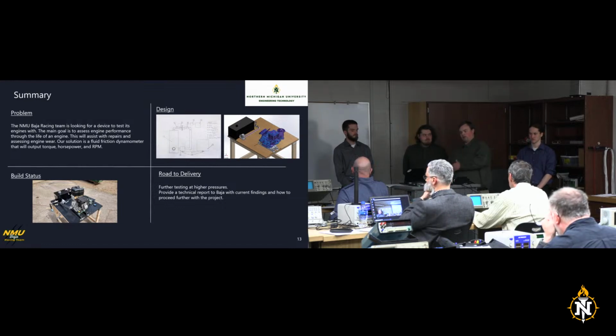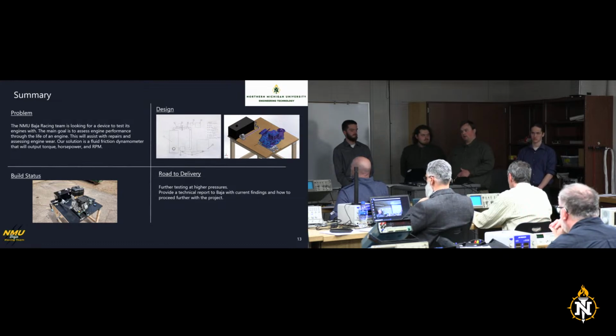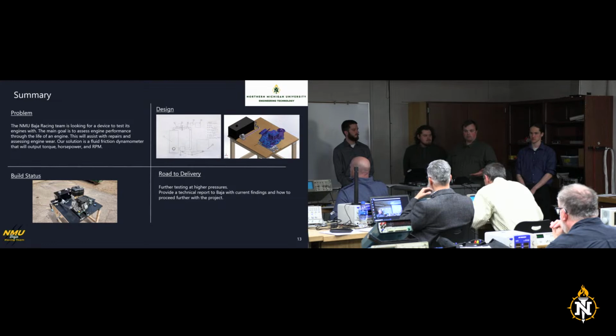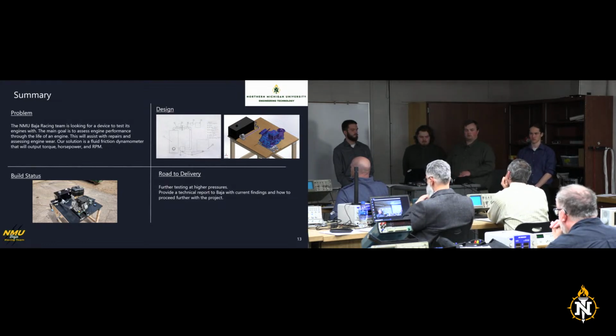in order to hit a power requirement of the pump that's similar to the rated power output of the motor at the given RPM. That way, if the pump requires 13 horsepower at 3,800 RPM, the motor outputs 13 horsepower at 3,800 RPM. That should sufficiently load the motor. We can actually notice a difference in the motor operation and measure the power output of the motor.